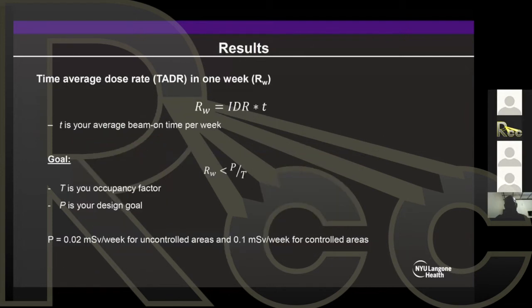So the second quantity is the time average dose rate in 1 week, RW. So this quantity you can calculate by multiplying that instantaneous dose rate by T, that is your average beam on time per week. And here is the one that you need to ensure. This is the measurement that you need to focus on to ensure your goal, right? So this measurement has to be lower than your design goal divided by the occupancy factor. Or you could just move this T here, like multiply your occupancy factor by your RW, and that has to be lower than your design goal.